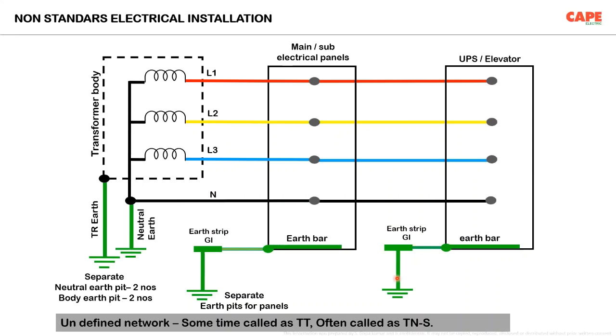The basic idea is people think that all unwanted current, which is going to create a hazard in the installation, goes to earth. If I have a bigger earth pit, what I mean is an earth pit with a very low resistance. Actually, we are not going to talk about this particular phenomenon. If your electrical installation is following this kind of method, the further slides are not related, or you cannot apply the principles written in the standard to this kind of electrical installation, where so many earth pits are applied and a very low resistance of the earth electrode is considered important.